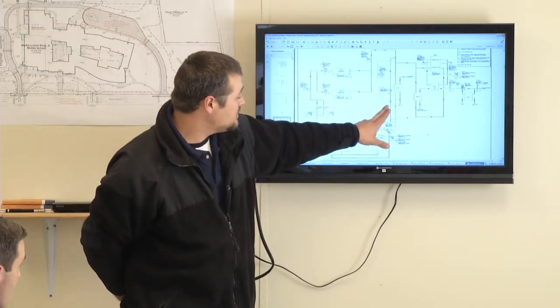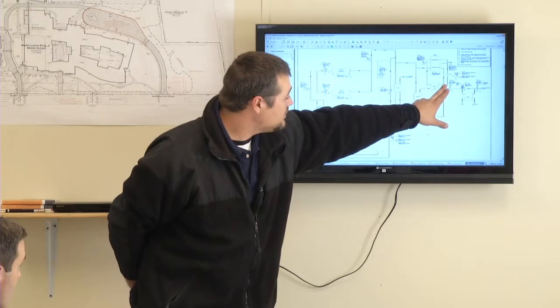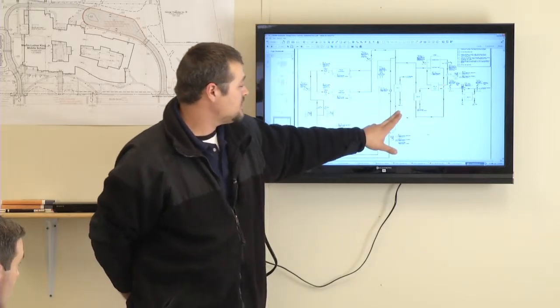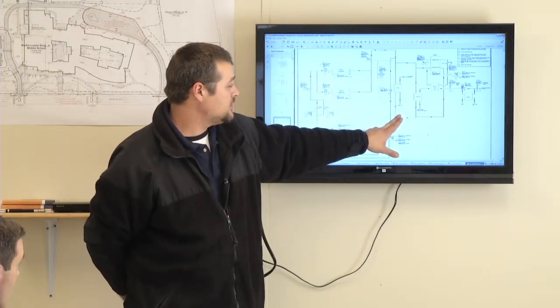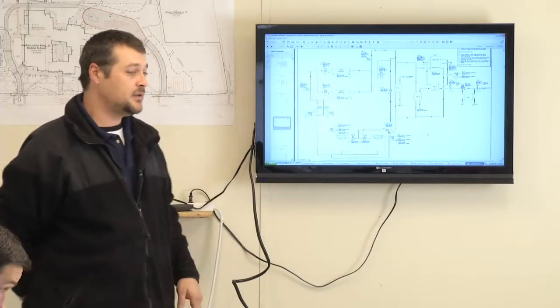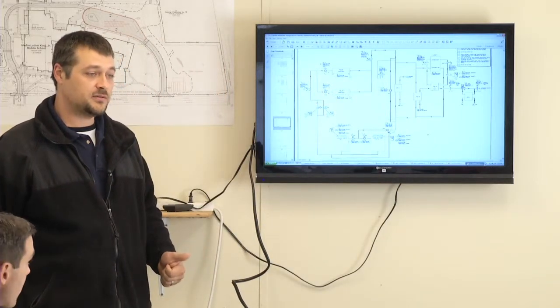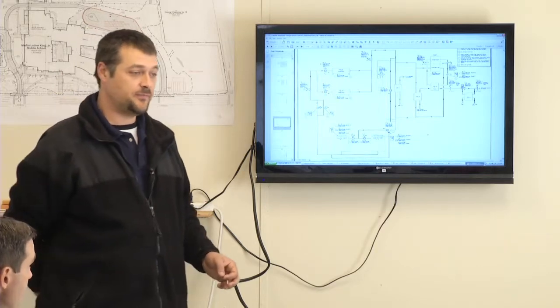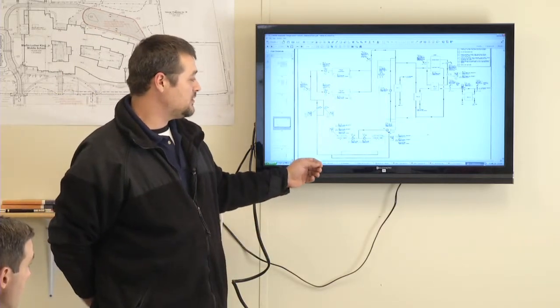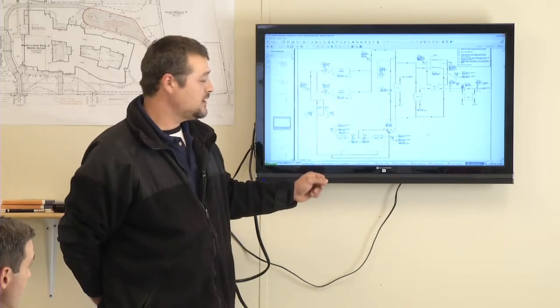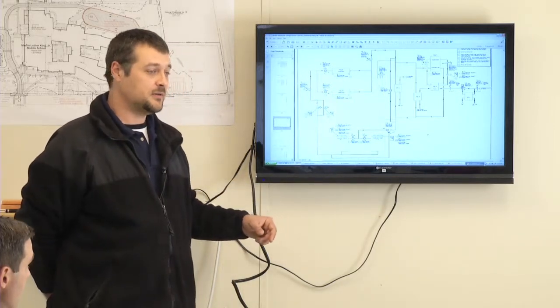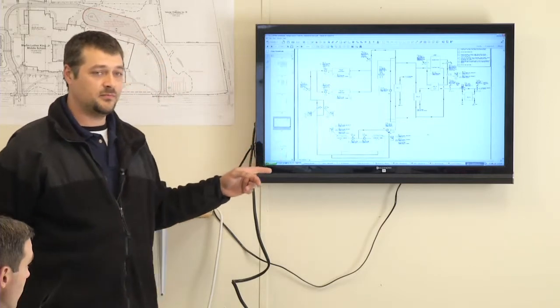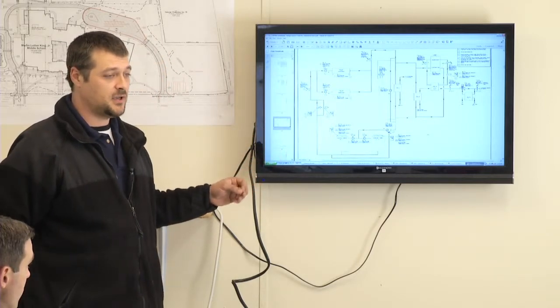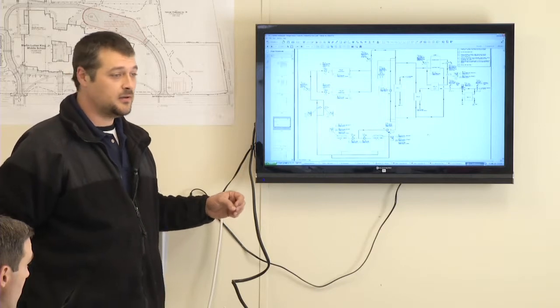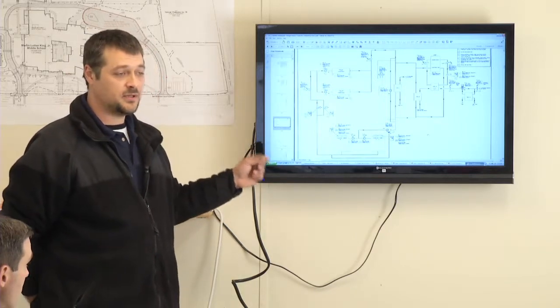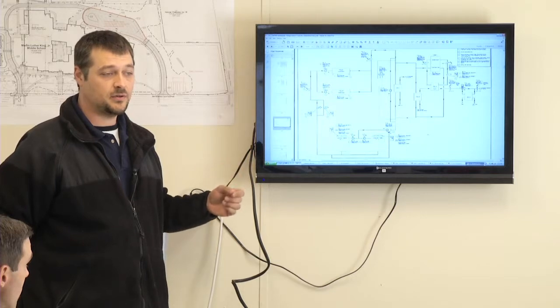The inline pumps, which we have on the heat recovery machine, pump 10, and there's also one not depicted on this drawing for the heat exchanger, pump 9. Those two have hardwired starts, but no speed reference. The only speed inputs that we have are for the cooling tower fans and then our secondary chill water pumps. The other speed references should be coded into the drives and should have been set by the balancer. The only thing we do with those is enable, disable, lead lag, and then monitor alarms.